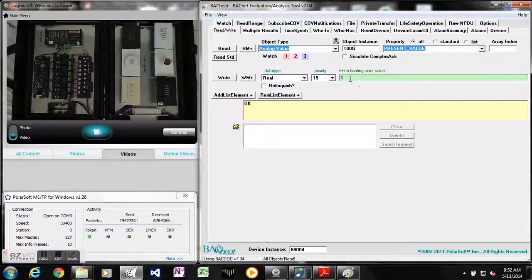So what we can do is I can start here at 33. So this would essentially be, if we had a 5th station, button number 1 on that station. So I can come up here and program for station number 5, button number 1, and I want it to cycle relay number 1, relay number 3, and relay number 5. So now I've programmed button number 1 for station 5 for kind of scene control. I want it to control relays 1, 3, and 5. So when I come back over here and I write that button press to there, it switches on relays 1, 3, and 5. Another press cycles them off. I set them for a cycle, essentially.